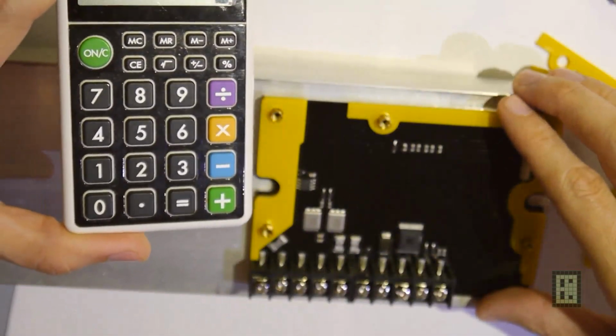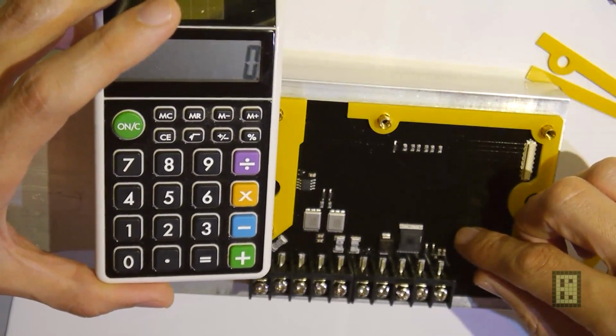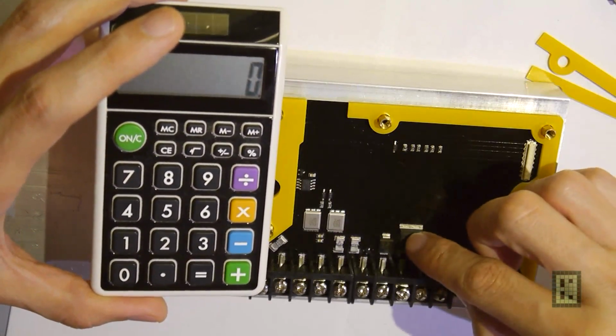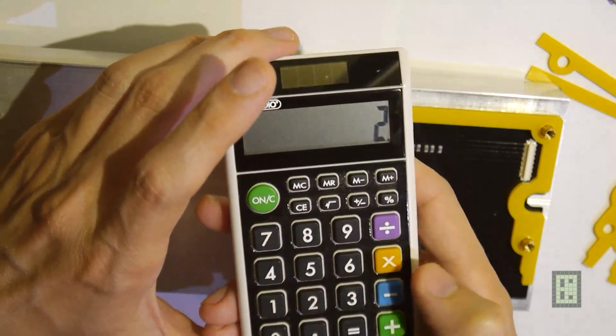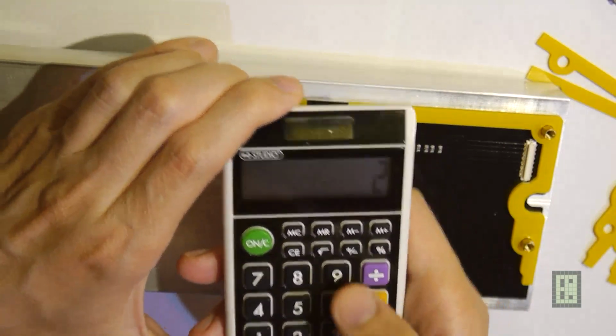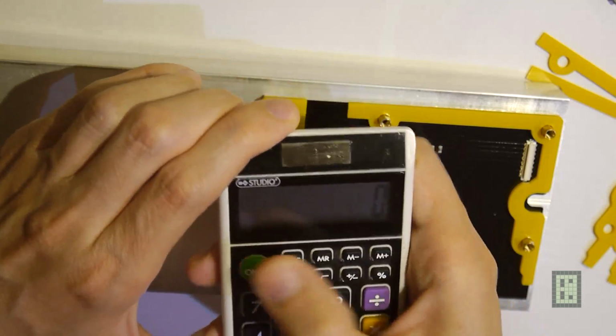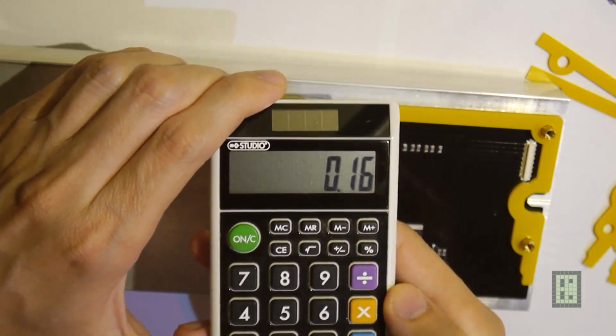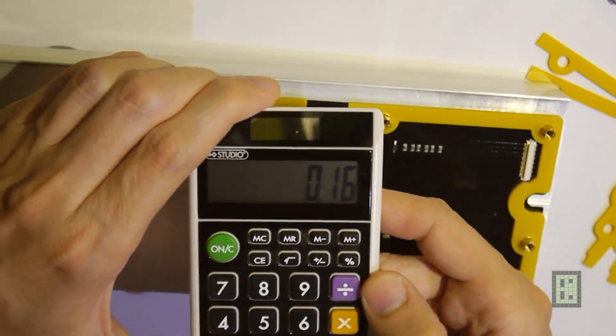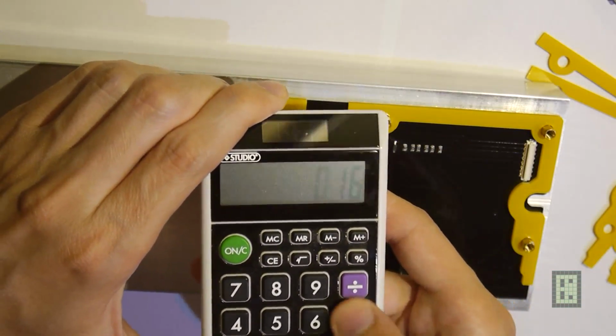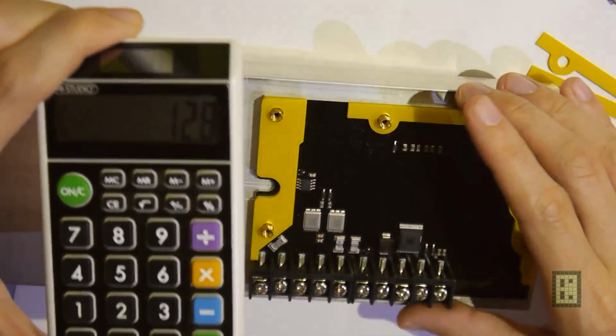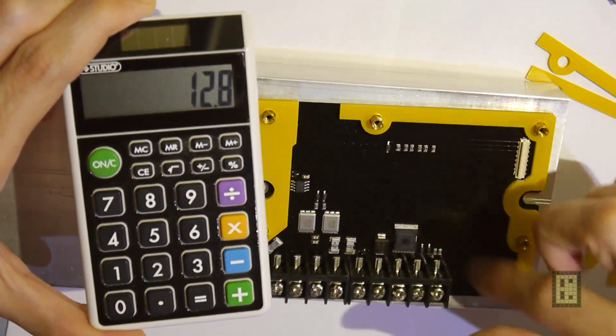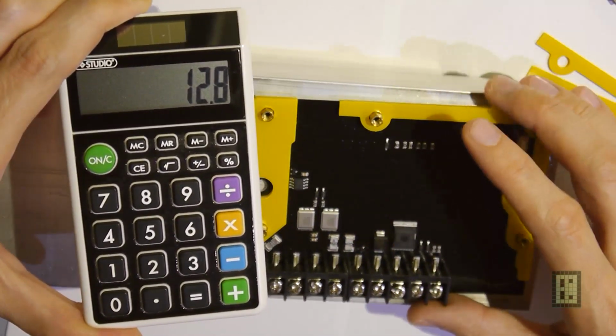Let's use a calculator. Let's say you want to use the maximum 80 amps on the discharging part, on the load, and like I said, you have a loss of 2 millivolts for each amp. So 2 millivolts multiplied by 80 amps gives you a total of 160 millivolt drop - 0.16 volt, which is the drop on this part, the load part. Then multiply this with 80 amps, like I said before, and it gives you 12.8 watts of heat that will be dissipated when you drive 80 amps to the load circuit part.